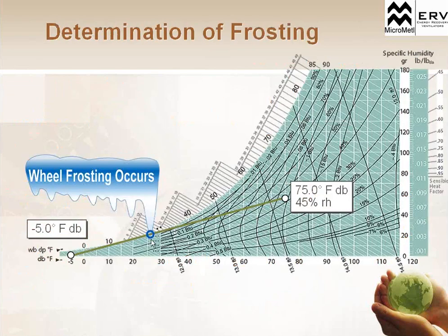We obviously do not want to freeze our wheel because we're going to lose all efficiency in the system. So there's a couple things that we can do normally. We can pre-treat our humidity, which would bring that line down as well, or we can preheat that outside air.